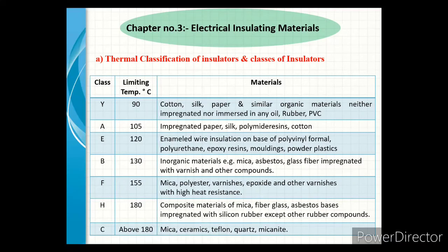Our seventh or last class is C class, and its limiting temperature range is above 180 degrees Celsius. The material included in this class is mica, ceramics, Teflon, quartz, and micanite.